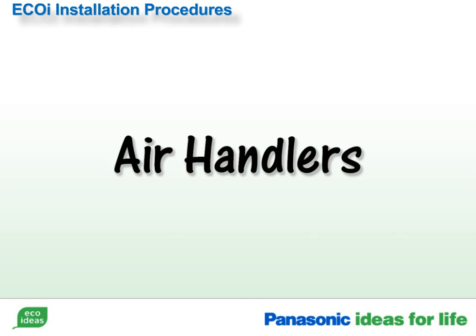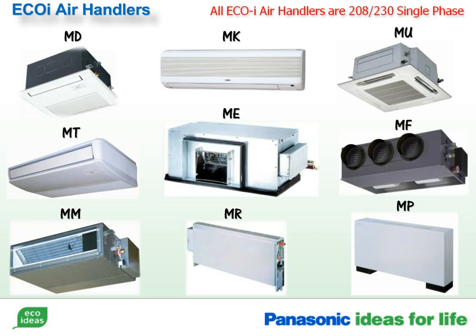Let's take a look at the air handlers available for Panasonic VRF system. Panasonic offers a variety of indoor units and they all operate on 208 to 230 volt single-phase power. The MD is a semi-concealed ceiling unit with a one-way air throw. The MK is a wall-mounted unit. The MU is a semi-concealed ceiling unit that has a four-way air throw. The MT is a ceiling suspended unit with a one-way air throw.